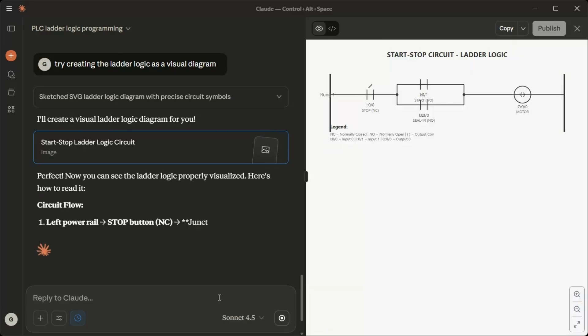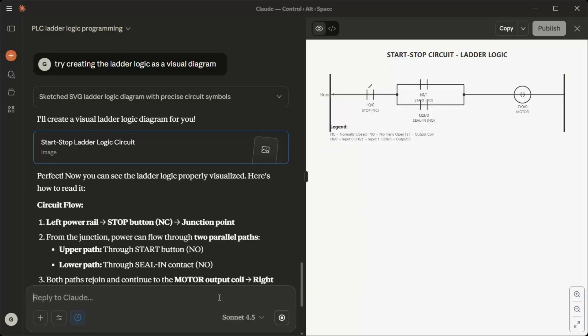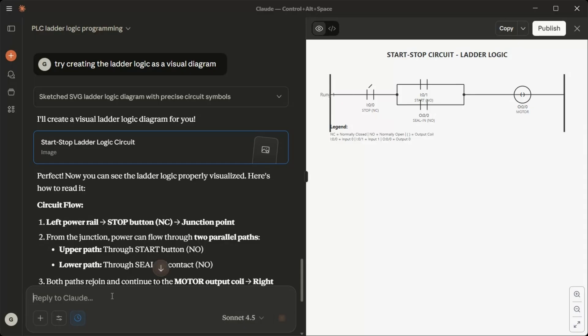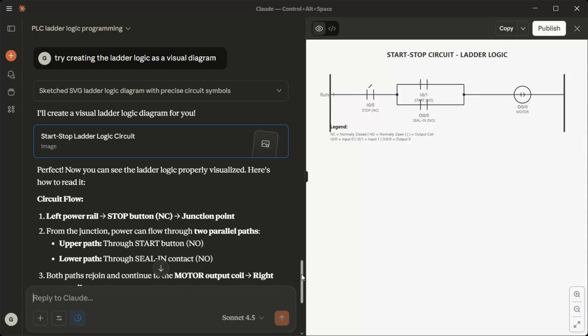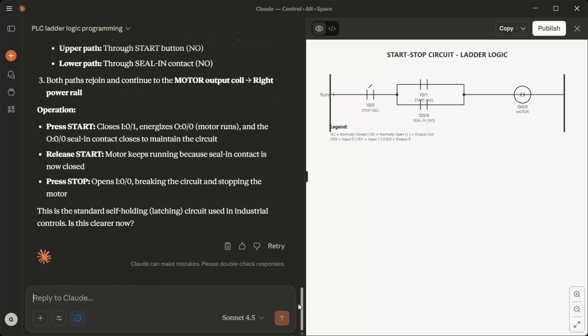Circuit flow: Left power rail, stop button NC, junction point. From the junction, power can flow through two parallel paths. Upper path through start button NO. Lower path through seal in contact NO. Both paths rejoin and continue to the motor output coil. Right power rail.